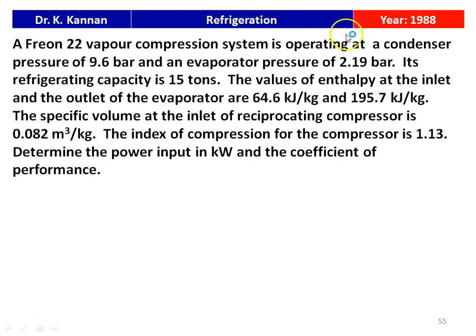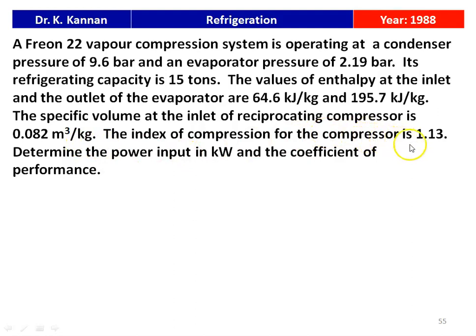The first question is from the 1988 question paper. A Freon 22 vapor compression system is operating at a condensing pressure of 9.6 bar and evaporator pressure of 2.19 bar. Its refrigeration capacity is 15 tons. The value of the enthalpy at the inlet and outlet of the evaporator are 64.6 kJ/kg and 195.7 kJ/kg. The specific volume at the inlet of the reciprocating compressor is 0.082 m³/kg. The index of compression is 1.13. Determine the power input in kilowatts and the coefficient of performance.